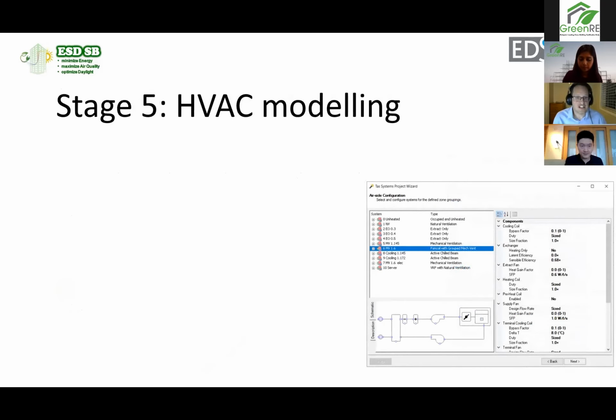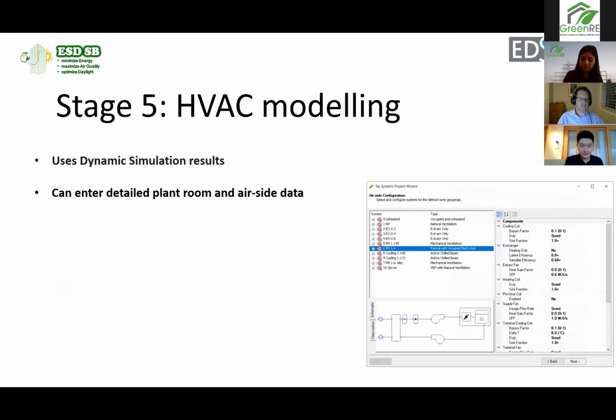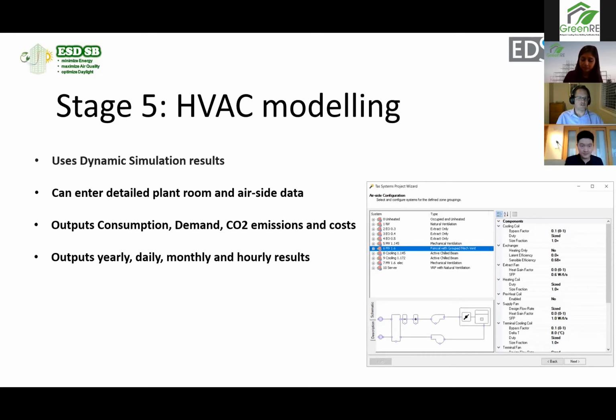The next stage is to model the HVAC system that is used by the buildings. It uses the results from the dynamic simulation that we would have already done, which gives us the loads and the temperatures within the space. The user can then enter detailed information about the plant room and about the air side. It outputs consumption, demand, CO2 emissions and costs. You can enter your own CO2 emission ratings and your own costings to get those values, and it outputs those results annually, daily, monthly and hourly.